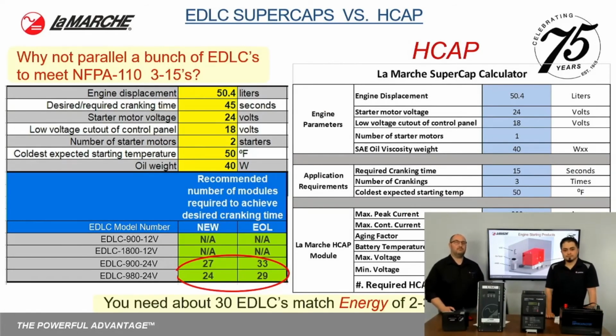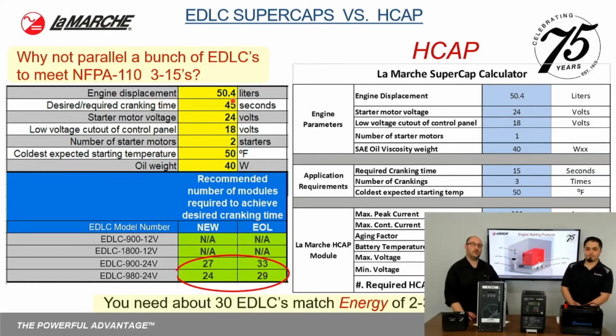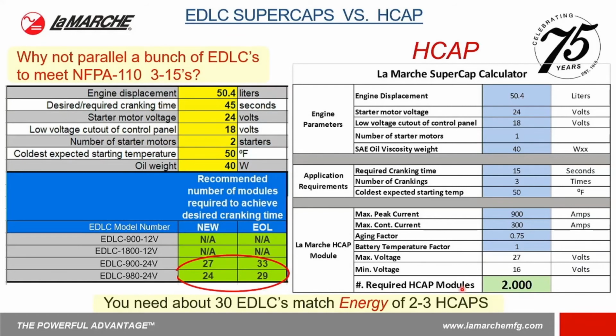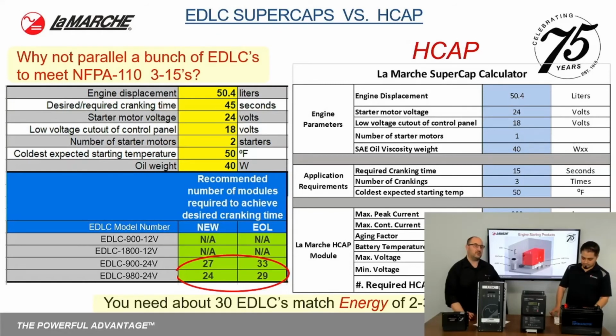Let's look at legacy EDLCs. Why not just parallel a whole bunch of them in order to meet the energy requirement, in order to meet NFPA 110's 15 seconds of cranking? So you could do that. It's possible, I guess, but let's take the same generator. Looking at an example that is a 50-liter engine, you're going to require approximately 30 EDLCs in order to match the energy of 2 or 3 Maxwell HCAPs. On this particular installation, I would actually recommend 3, but still, approximately 30 EDLCs versus 3 HCAPs. That's a big difference, not only in price, but also in volume. There's nowhere to fit 30 EDLCs in that small trailer.